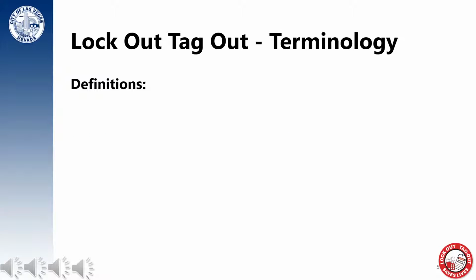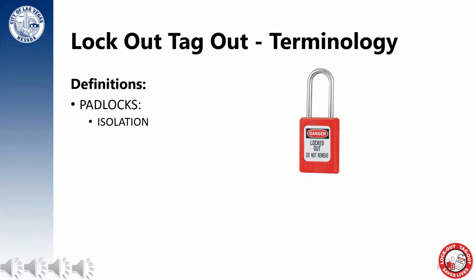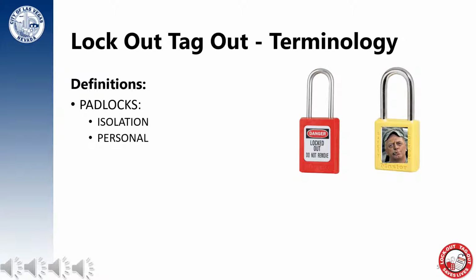One of the new changes will be the definition of padlocks. Isolation padlocks are what operations will be using to lock out devices. Operations will have a common set keyed-alike padlock to apply to energy isolating devices, whereas your personal padlock, what you're used to using, will be added in addition to the isolation padlock provided by operations. Operations will lock out, and you will follow with your personal padlock.